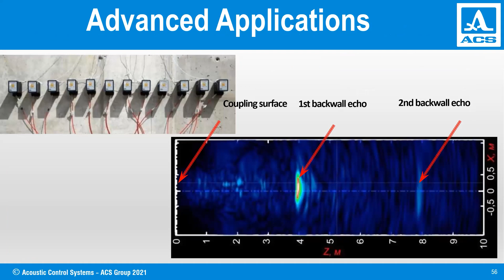By its nature, the dry point contact transducers possess a matrix aperture, and in the previous generation of ultrasonic instruments, those matrix apertures have never been used as matrix apertures. Actually, we always connected several elements together and used this aperture as a linear transducer array. If we really apply the data acquisition electronics individually to each element, we will be able to perform real, true three-dimensional tomographic imaging. Then, in the scope of this implementation, we can also improve crack sizing functionality, for example, for open cracks, which I will exemplify now.